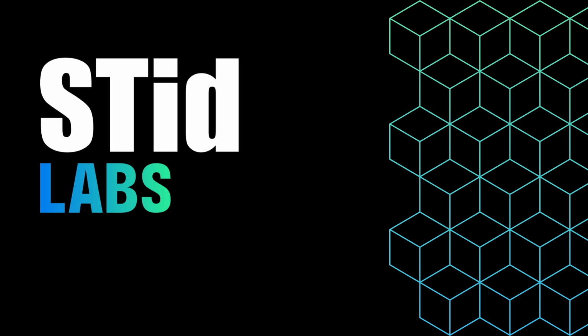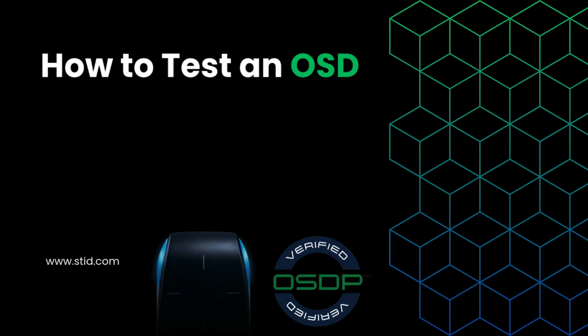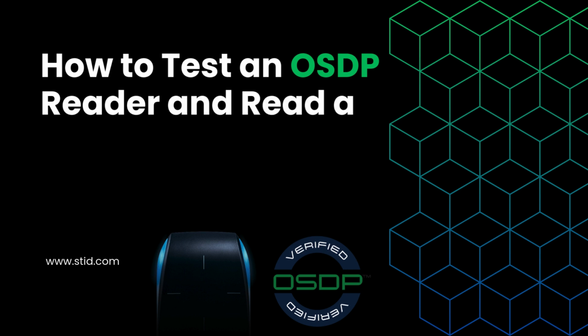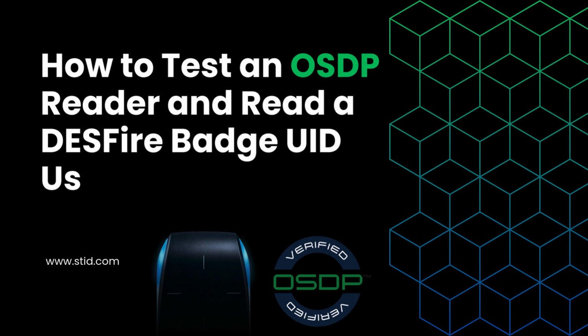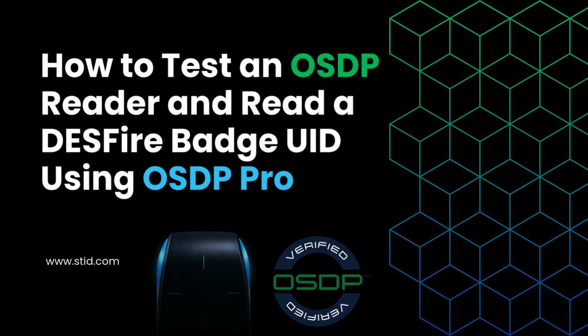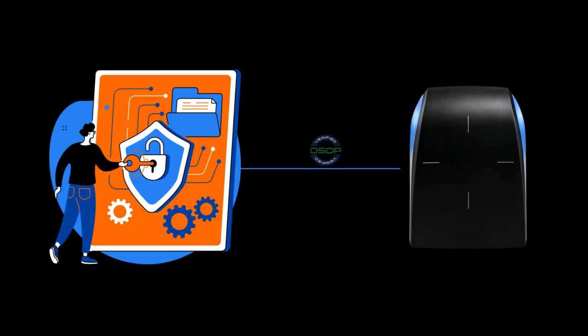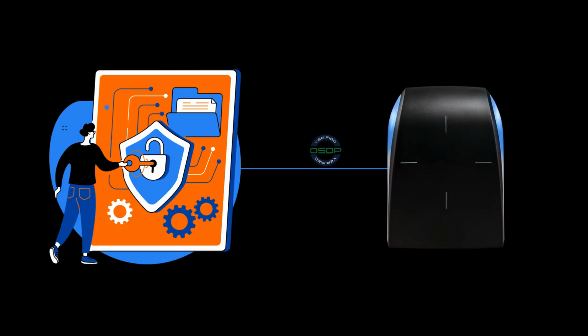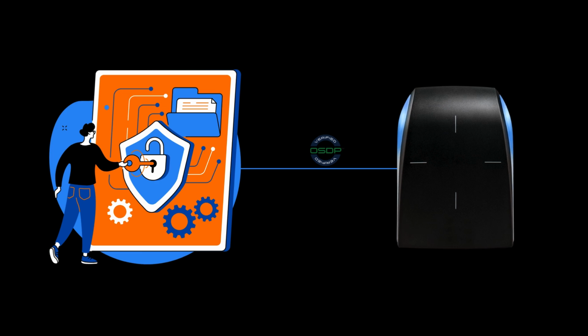In this tutorial, we will demonstrate how to test an OSDP reader using our OSDP Pro tool, specifically by reading the UID number of a DESFire badge. This is useful if you'd like to perform a read test before connecting your reader to an access control system that will manage the reader via OSDP commands.